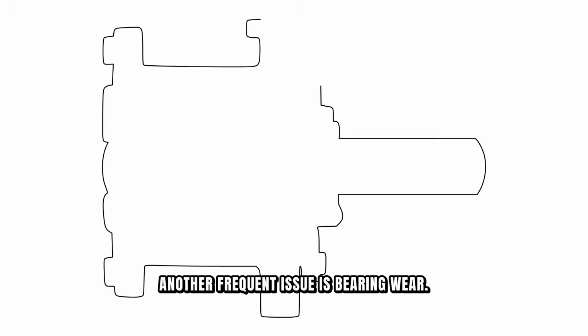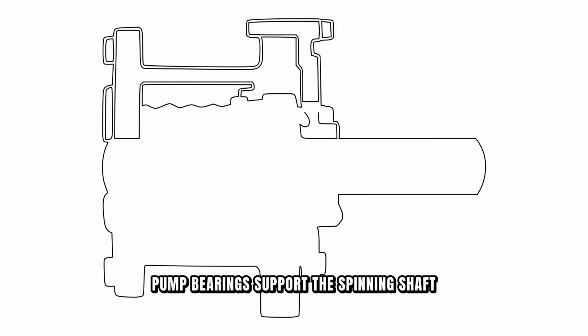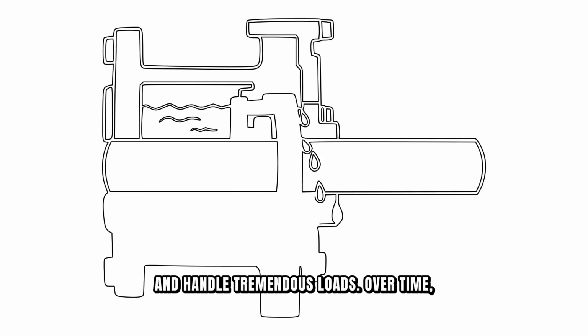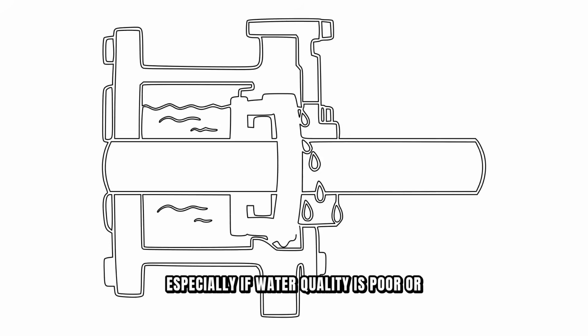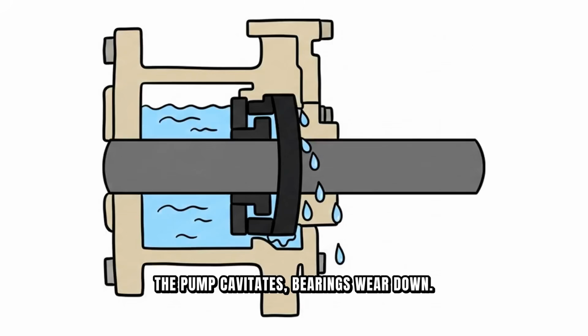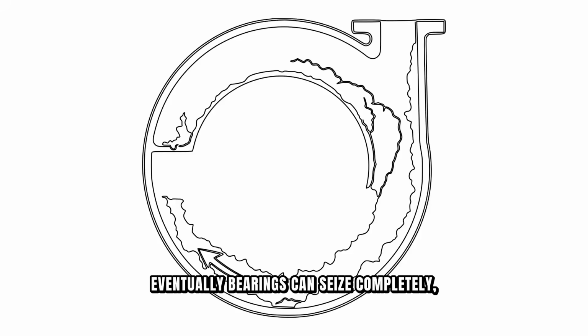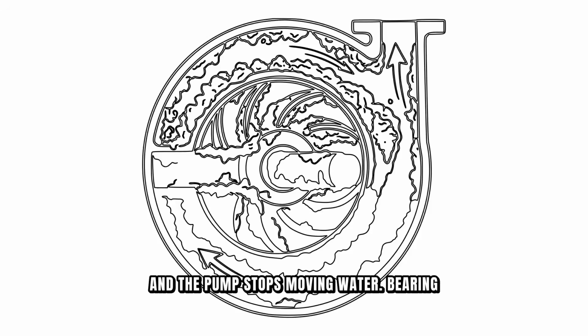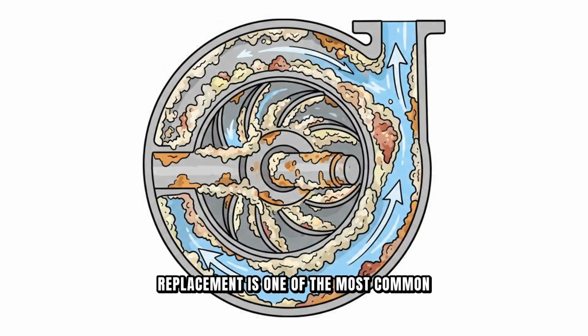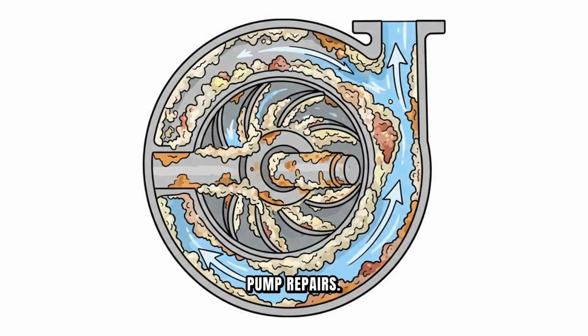Another frequent issue is bearing wear. Pump bearings support the spinning shaft and handle tremendous loads. Over time, especially if water quality is poor or the pump cavitates, bearings wear down. You'll notice increased vibration and noise. Eventually, bearings can seize completely, and the pump stops moving water. Bearing replacement is one of the most common pump repairs.